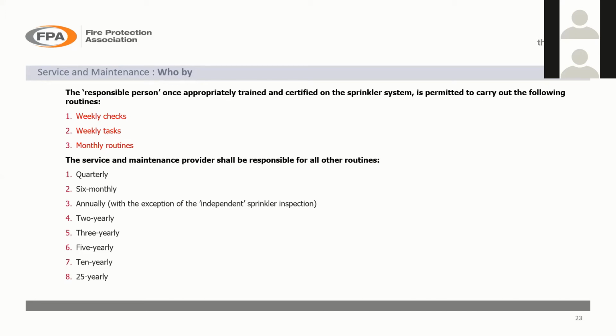Sometimes what we see, when we go along, is that a maintenance contractor might be looking after the building, and he's maybe done that for 10 years or 20 years. And we live in a commercial world, so these guys quite rightly come back when they're doing a good job for you. But sometimes what we find is that they're no longer maintaining the system, A, in accordance with the latest standard, or B, in accordance with the latest rules. There might be valve sets that don't get tested or serviced by them because they're unaware of it, and also some of the routines that are in the rules, such as review of hazard, which is one of the requirements of the standard. It's not always carried out, and sometimes that can be in the contract, when you look at it, either omitted or actually excluded by the contractor.